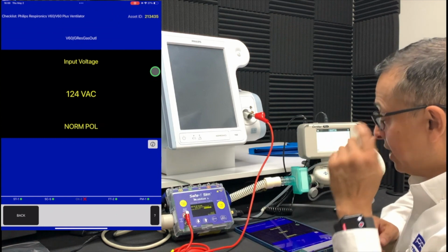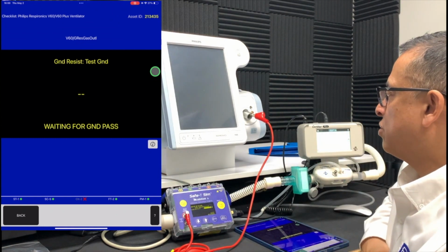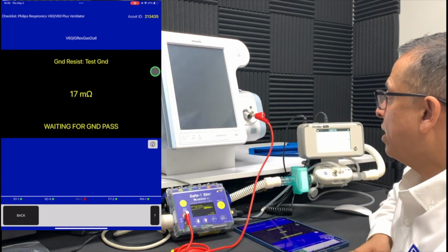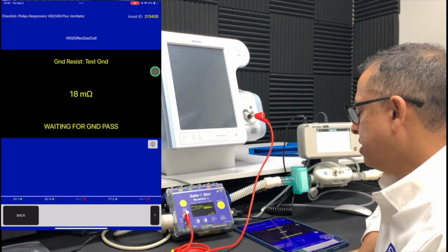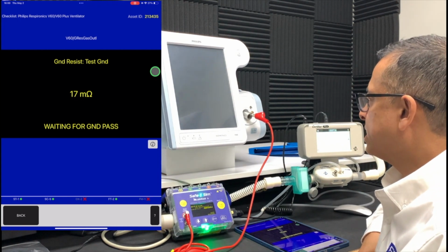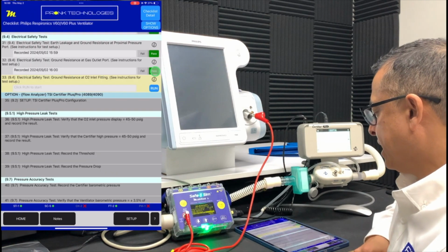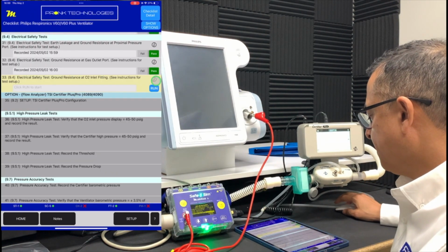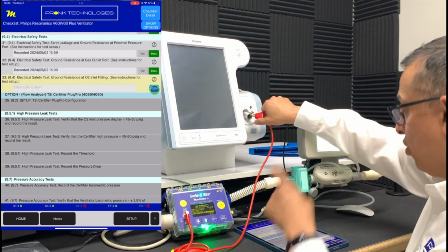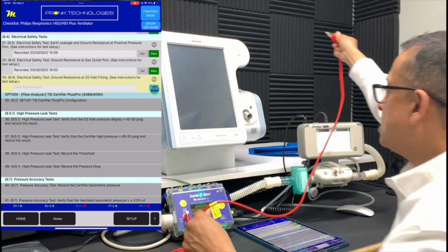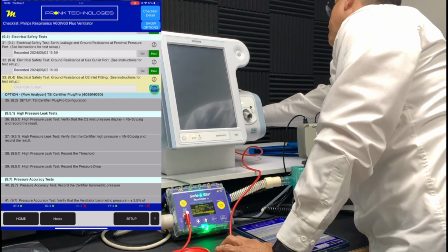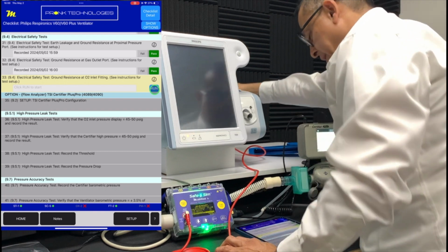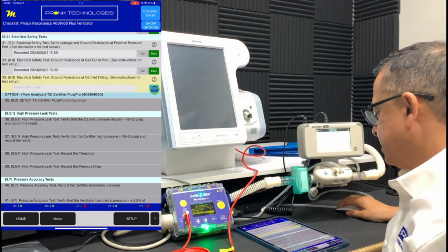They want to make sure that we're testing that ground resistance on anything that in theory could come in contact with the patient. So we want to test those ports as well. You can see we've done that next test, and it's collected that individual result. We also need to do it on the O2 inlet, which is on the rear of the unit. So we would connect this to the back of the unit here, and then I would run that next test.